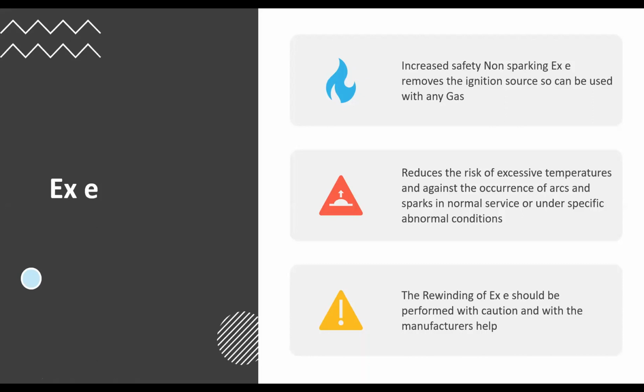An EXD can arc and spark and have a little explosion inside it all the time because it's the outside concept, the build concept, which is the protection level. This is taking the flint out of a lighter, if you like. It will not arc or spark, no matter how much it tries.